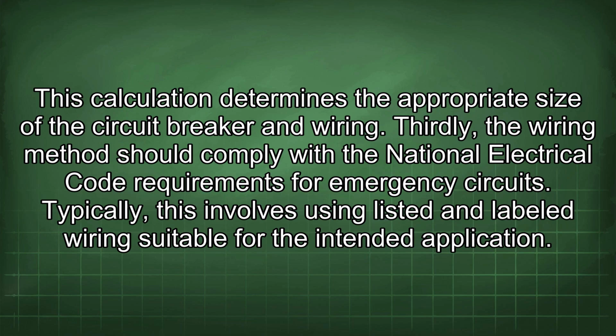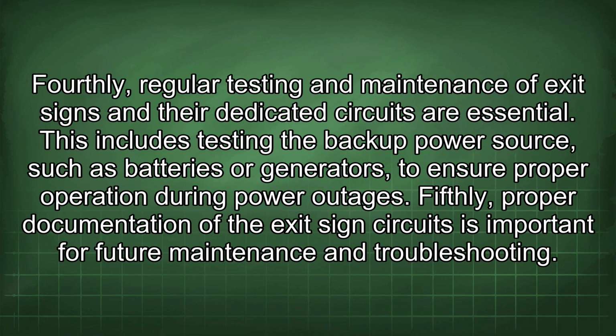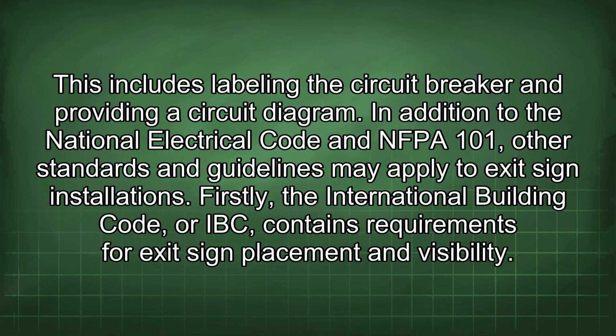Thirdly, the wiring method should comply with the National Electrical Code requirements for emergency circuits. Typically, this involves using listed and labeled wiring suitable for the intended application. Fourthly, regular testing and maintenance of exit signs and their dedicated circuits are essential. This includes testing the backup power source, such as batteries or generators, to ensure proper operation during power outages. Fifthly, proper documentation of the exit sign circuits is important for future maintenance and troubleshooting. This includes labeling the circuit breaker and providing a circuit diagram.